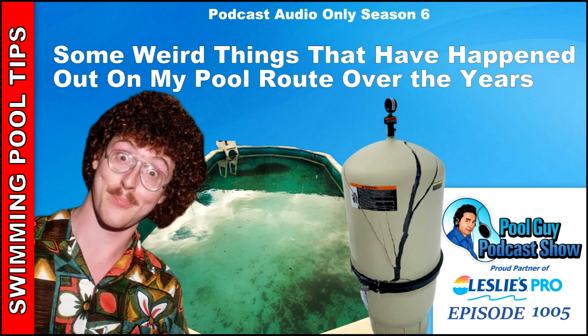And then I'm standing there in front of the filter, and I'm looking at this filter, and it's a Quad D filter. And I'm just looking at it very carefully, and I realized that the person that installed this filter actually has the inlet and outlet reversed. If you know anything about the Quad D filter, the inlet and outlet are the same as a cartridge filter and not a DE filter.